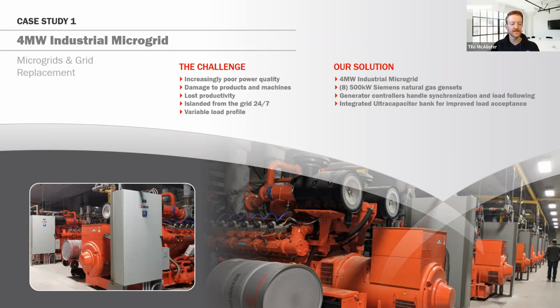Now, in this particular project, it's just power generation. If you're familiar with generator efficiencies, converting natural gas into useful electricity is actually not a very efficient process - somewhere between 30 and 40% of the energy in the fuel actually ends up as usable electricity on your wire, and the rest is primarily lost as thermal energy, heat, in the exhaust and in the coolant that goes to the radiator.